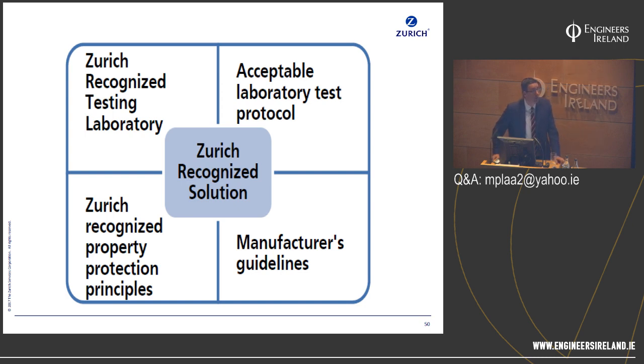Back home we don't really have such things as certified water supplies, and it's a big challenge in many parts of the UK around what the water undertaker is supplying to that site. Sometimes the water supply just isn't sufficient in terms of pressure, and you're looking at some kind of boosted supply as well. From a commercial industrial point of view, as an insurer, we always recommend pump and tanks, because we've seen, especially in England, a reduction in town's mains pressures across many counties, which has impacted on the town's mains system's ability to provide the necessary pressures and flows. So we would recommend against relying on the town's mains municipal supply.